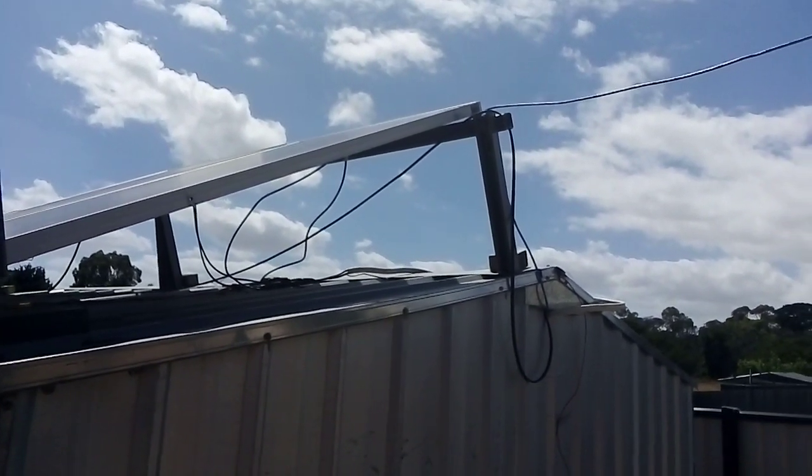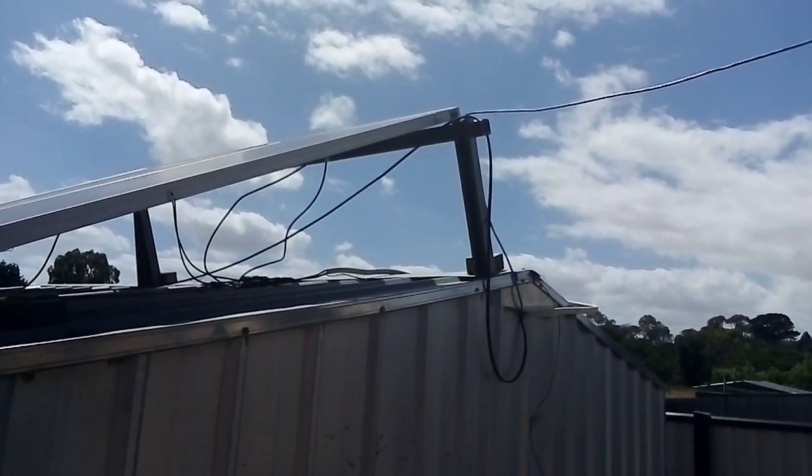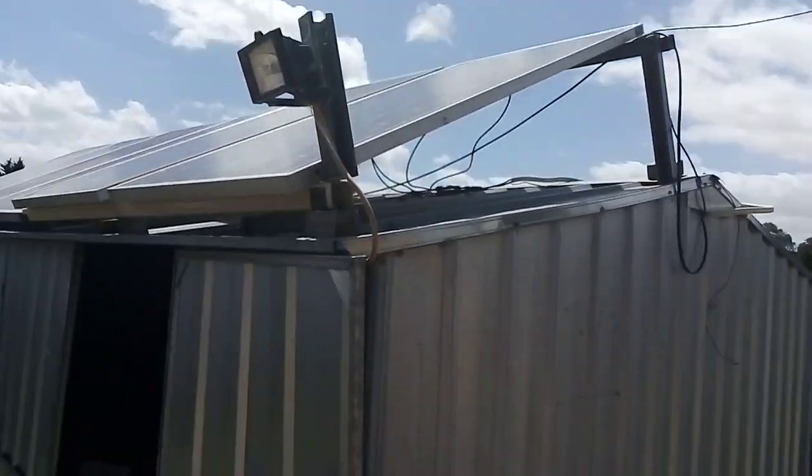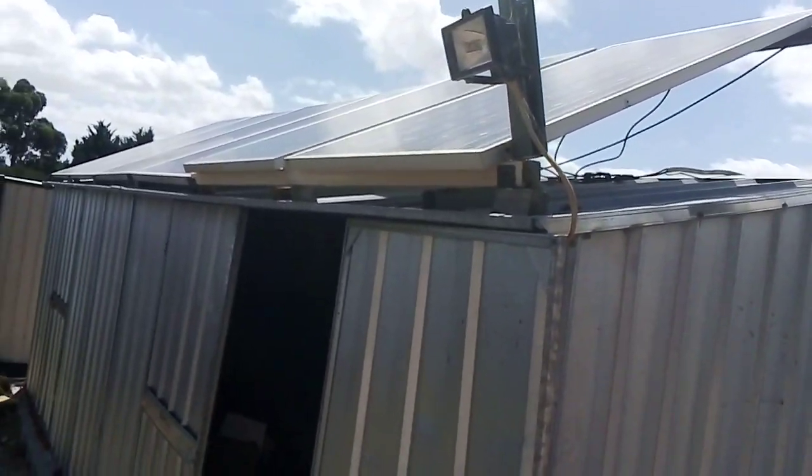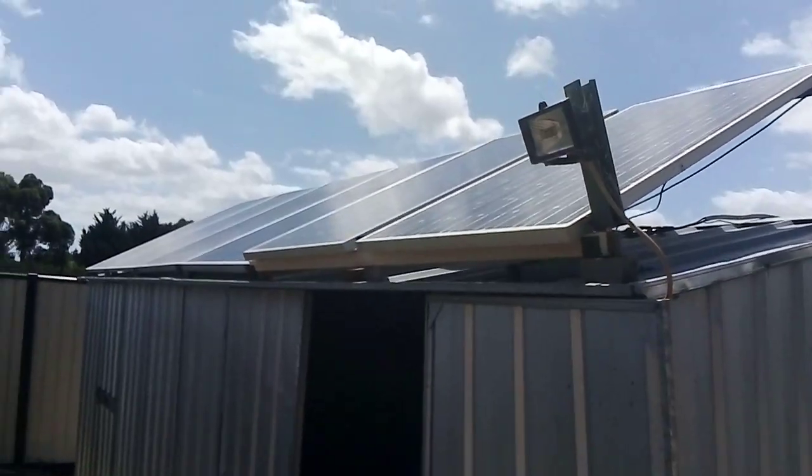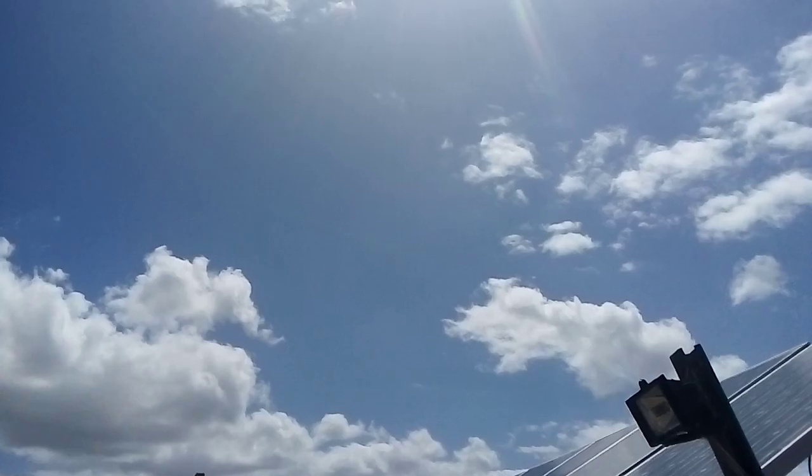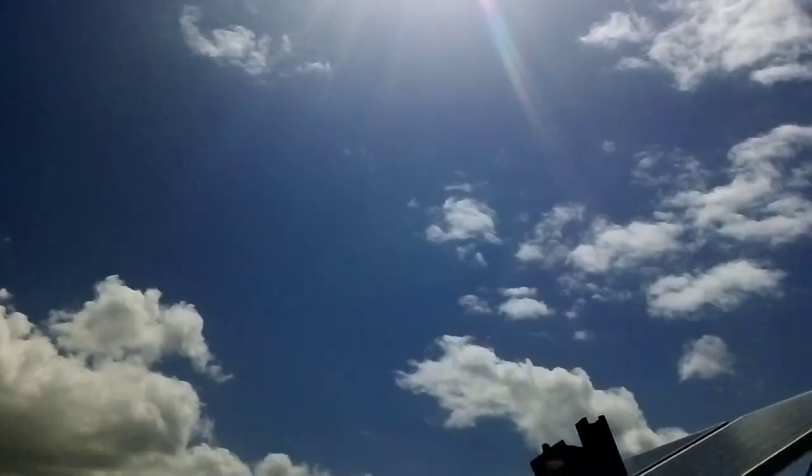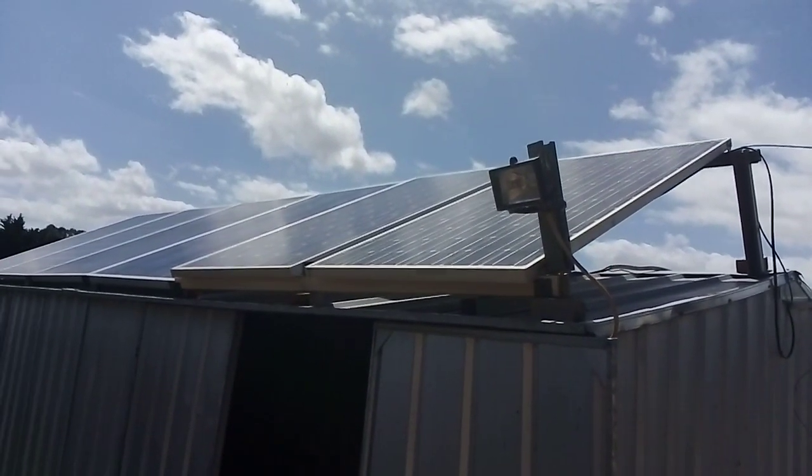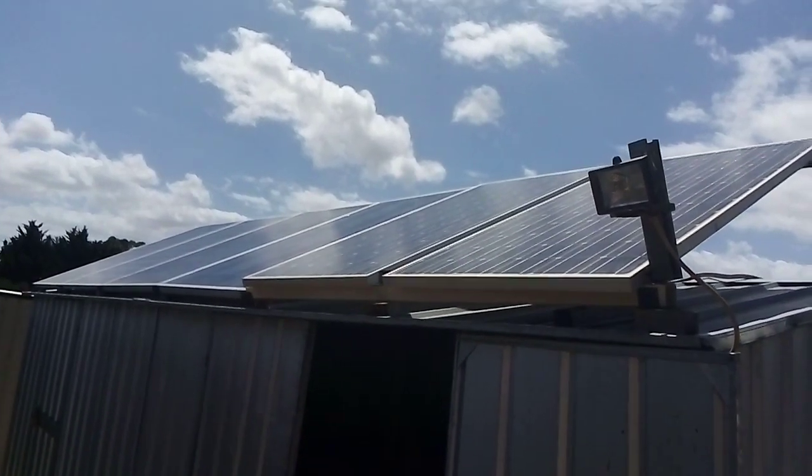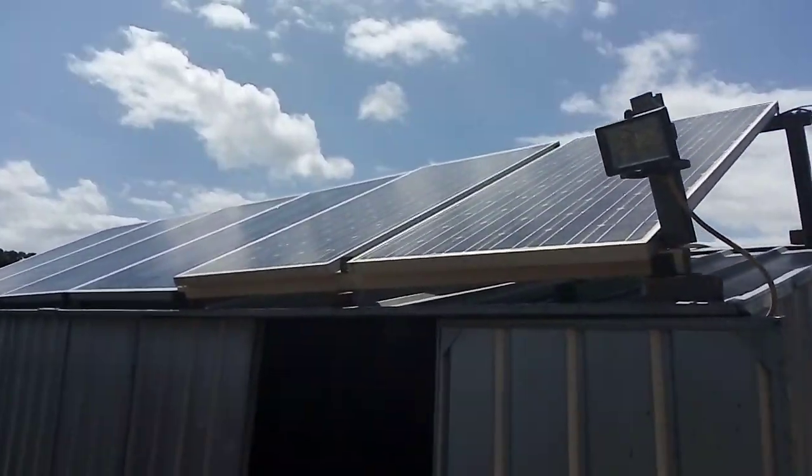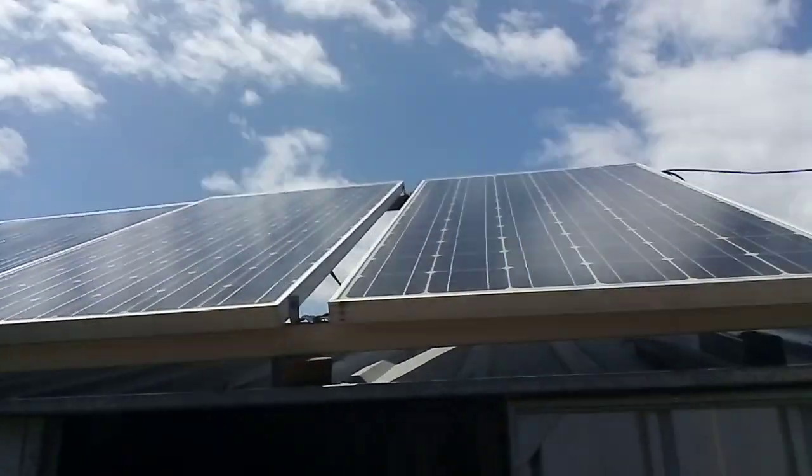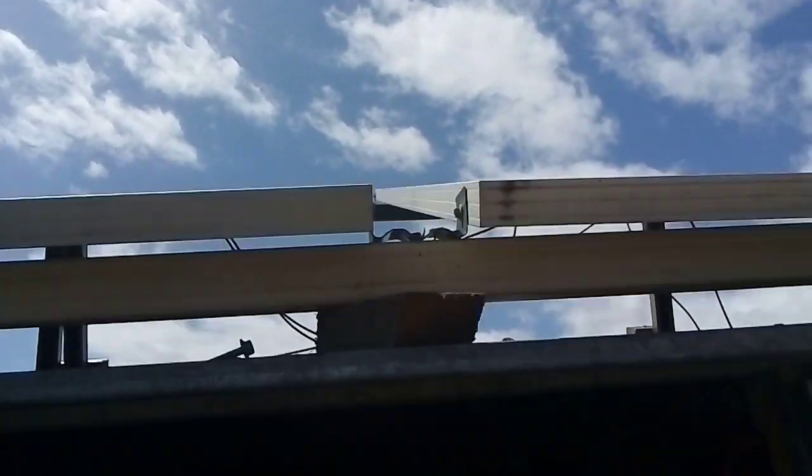At the moment this is facing west. It's about 12 o'clock now. The sun is not quite 90 degrees to the panels. On paper these are about 1400 watts, but we're doing about 900 at this time. I'll show you what this looks like on paper and how to calculate.